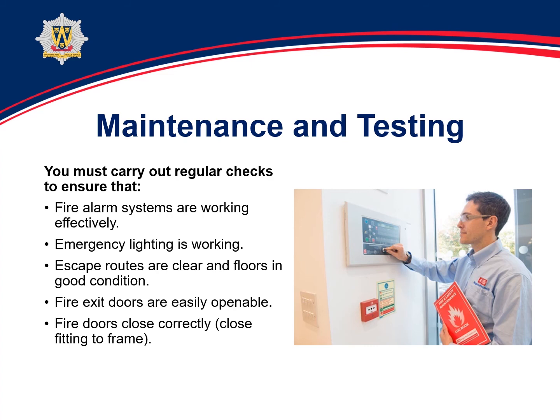The fire doors that protect the escape routes, that have those intumescent strips and smoke seals, make sure they are closing correctly and close fitting into the frame. If fire doors are held open for any reason with automatic hold open devices or releases, make sure they're working because holding them open can weaken the springs and the self closers may need adjusting from time to time.